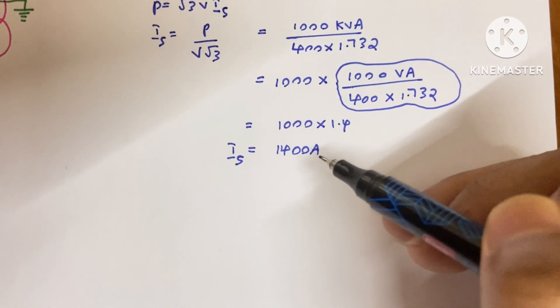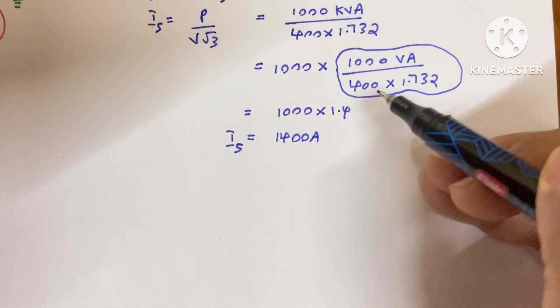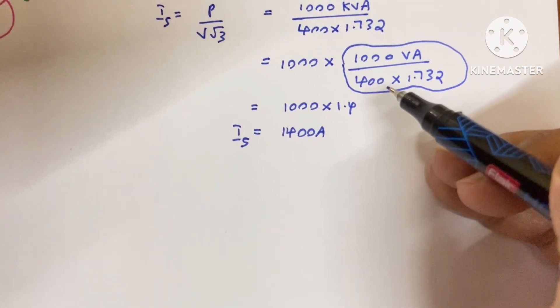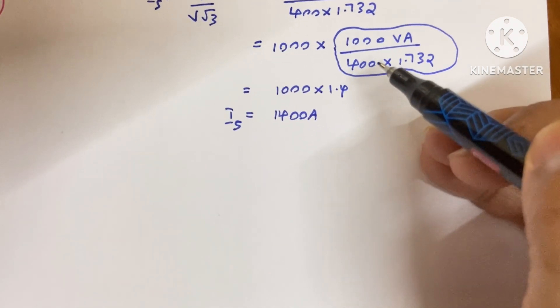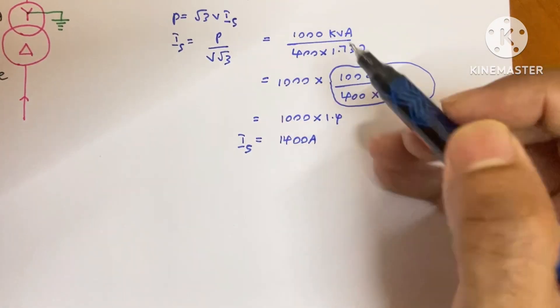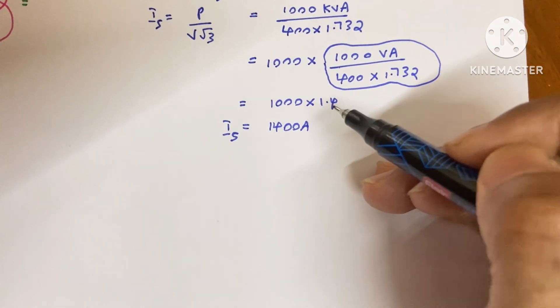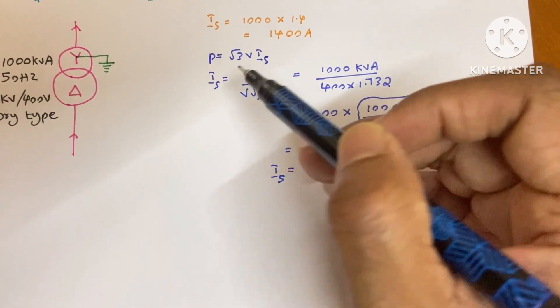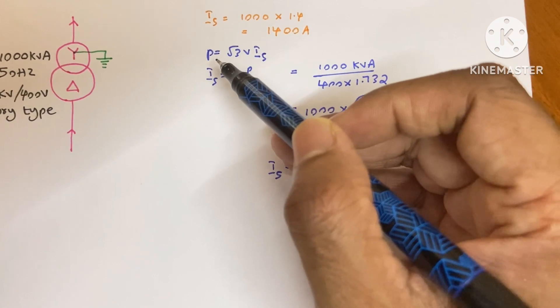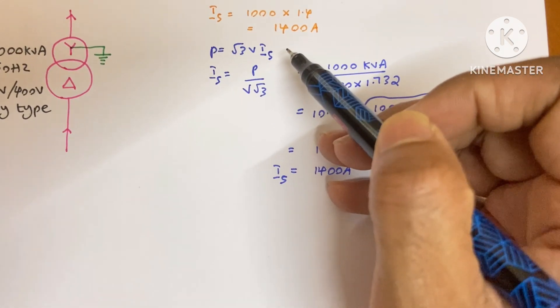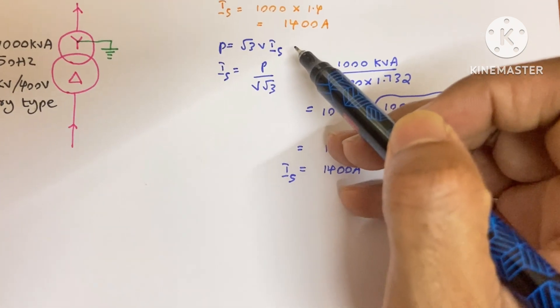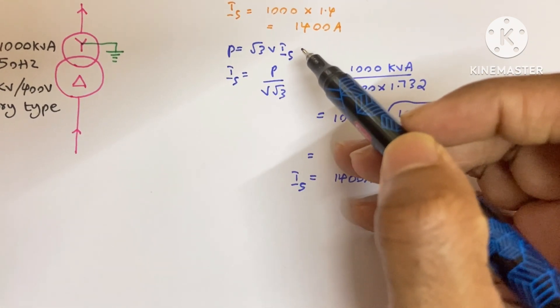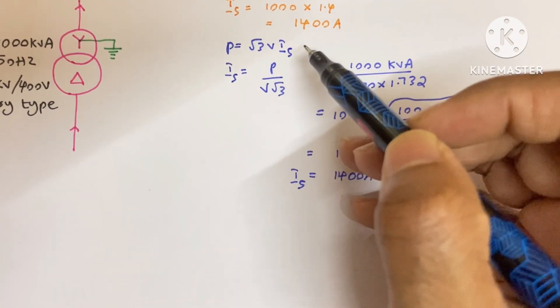One important thing to remember: this 1.4 is valid only if the secondary side voltage is 400 V. If your transformer's secondary voltage is different, you need to work through the full equation to find your own magic value — it will be different. Also, our power here is in kVA, so we do not need to include cos theta or power factor. Power factor is only required when the power is given in kilowatts.